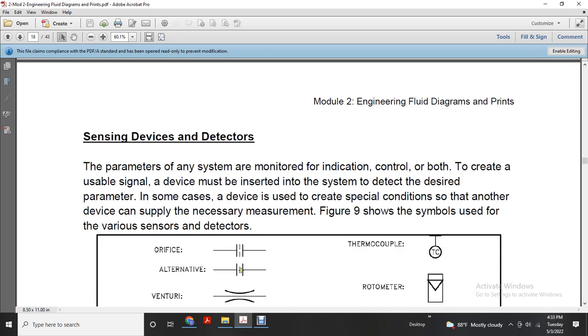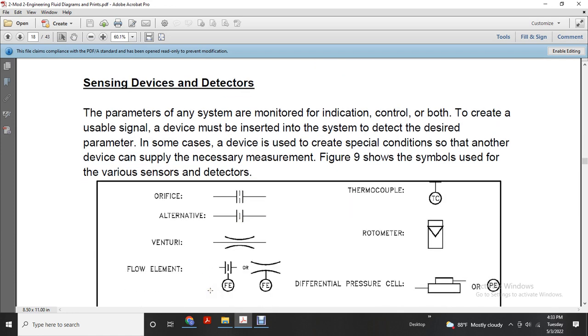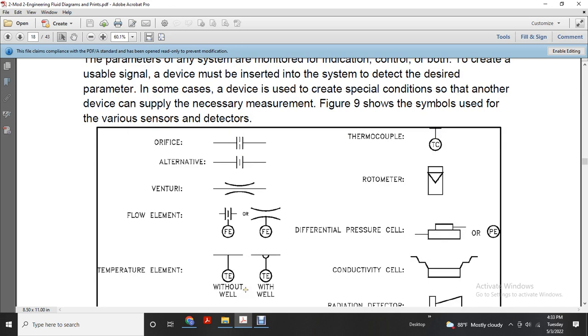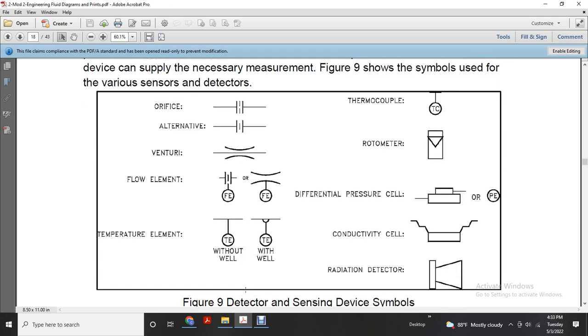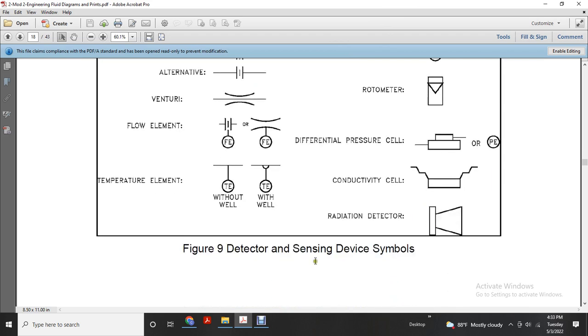Alright, you have your orifice and alternatives, and then the venturi, which looks like a restriction. A flow element is given with a restrictor or an orifice, labeled FE. Then the temperature element, TE: a junction without a well, with a well, TE in a circle, a thermocouple, TC on a bulb, a rotometer, a triangle with a square in it, a pressure differential cell, a large box and a lower box, or PE for pressure cell, a conductivity cell, and a radiation detector.